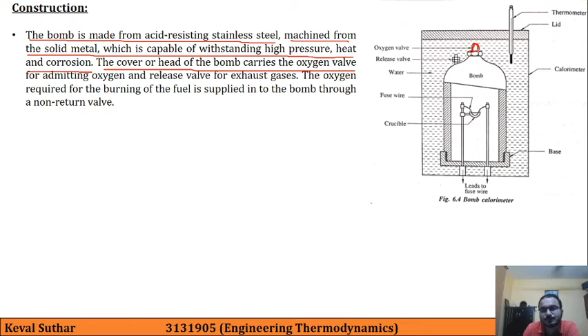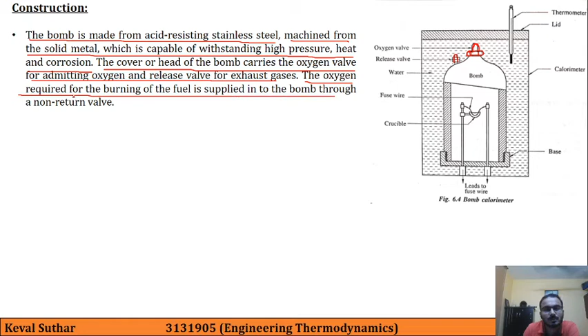Over here this is the oxygen valve for admitting the oxygen, and the release valve is for exhaust, to release the exhaust gases. Obviously oxygen is required for combustion of fuel, that's why oxygen is provided here, and the release valve is for the exit of exhaust gases or flue gases. The oxygen required for burning of fuel is supplied into the bomb through a non-return valve, that is this oxygen valve. Now let's focus on this crucible that is shown over here.